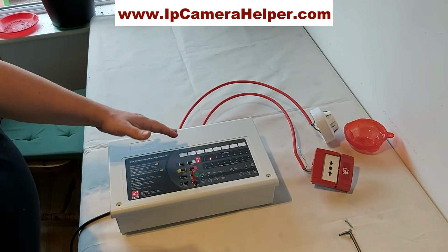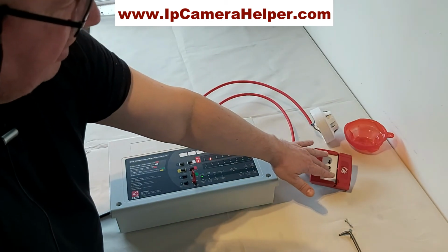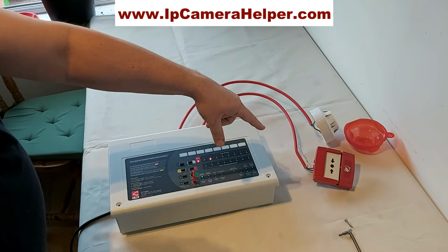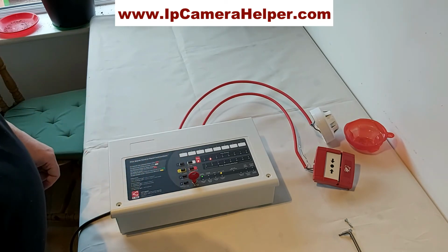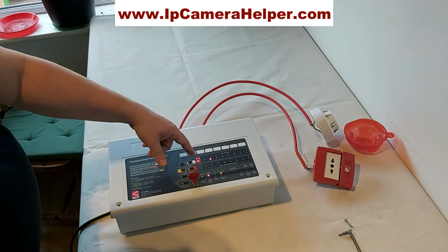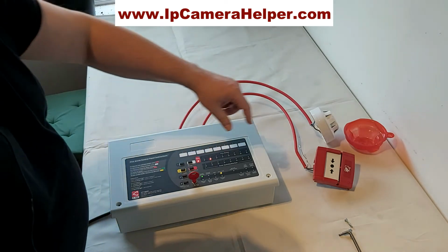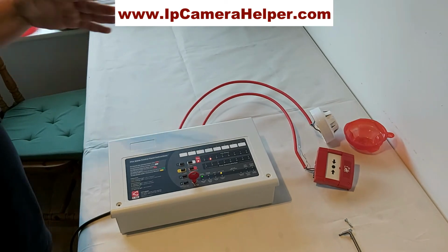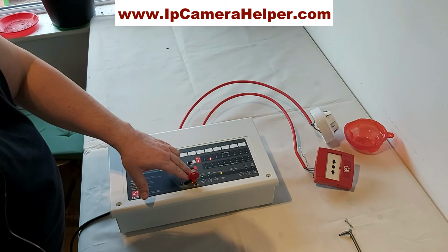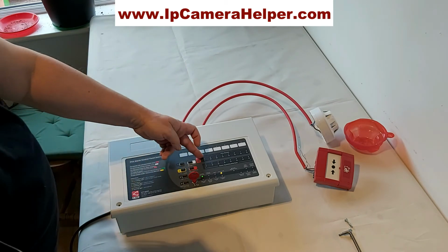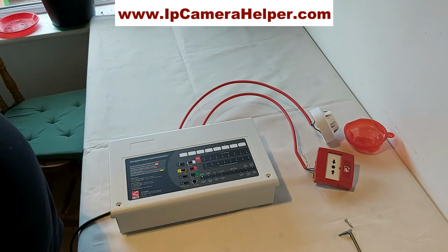Obviously we go around the building and identify the problem. That's our problem. So for us to reset it, we have to fix this one first. But I can try, just to show you that it won't reset. So I will reset it, and we're back where we were. So I reset the panel, but then the fire kicked in again. To reset it, we have to fix the problem, so there's no fire and all the break glasses are reset properly. Once it's done, now you can reset the panel, and the fire condition is gone and not triggering again, and we can turn the key to position 0, and the panel is nice and quiet.